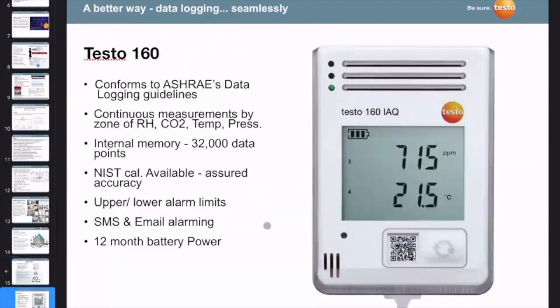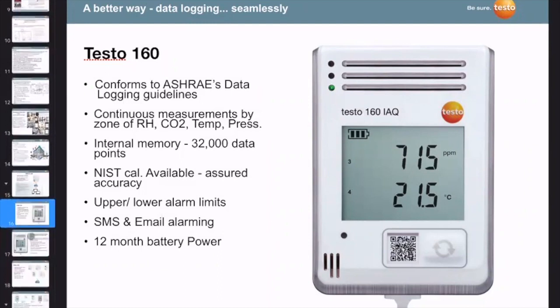When we look at some of the capabilities of it, the unique characteristic of this Testo 160 is its ability to actually collect and hold data. So 32,000 data points can be collected and transmitted to the cloud, and then can be viewed in report form by the administrators or the PTO or PTA individuals. There are 4 sensors located inside this enclosure, making it quite a compact package. And you can have upper and lower alarm limits set that can be sent out either as an SMS text message or as an email alarm message to the responsible parties. And again, 12-month battery power, which is quite an advantage as opposed to putting in a complicated wired system.